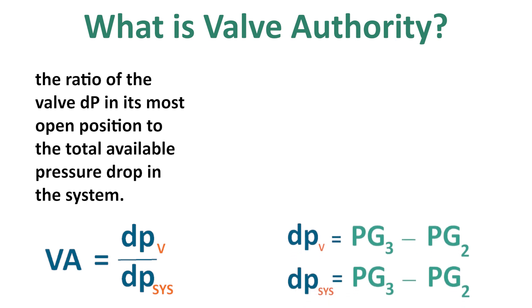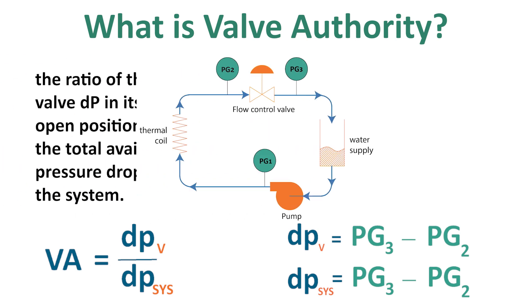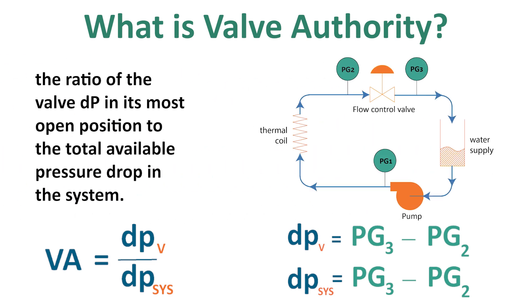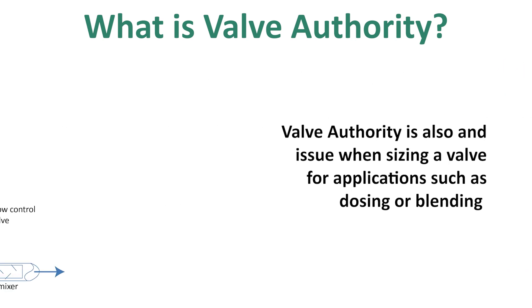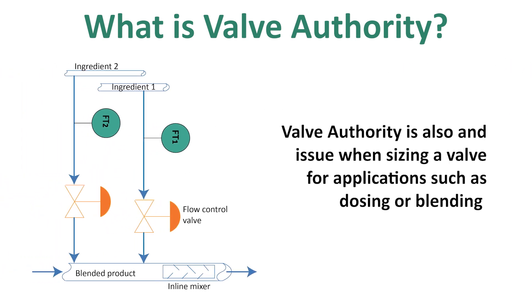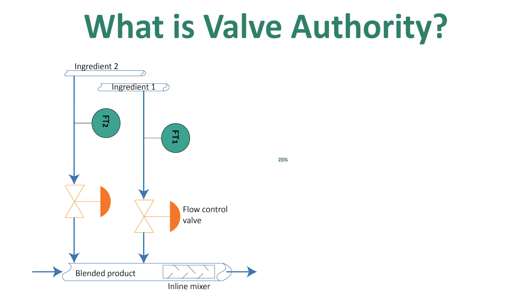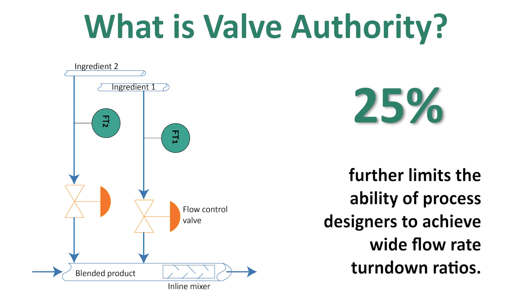This problem is commonly faced in hydronics, or the control of thermal water circulating loops. In these systems, significant energy is lost by sizing valves to always consume 25 percent of the pump's energy. Valve authority is also an issue when sizing valves for applications such as dosing or blending. This 25 percent lower bound limits the flexibility in valve selection and further limits the ability of process designers to achieve wide flow rate turndown ratios.